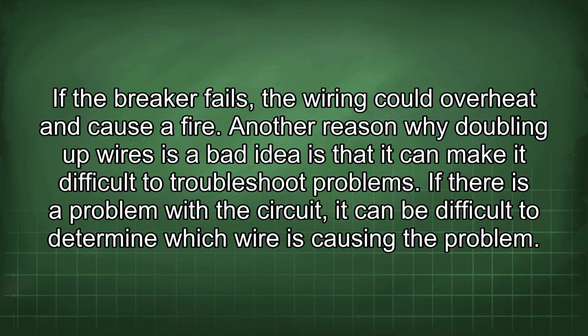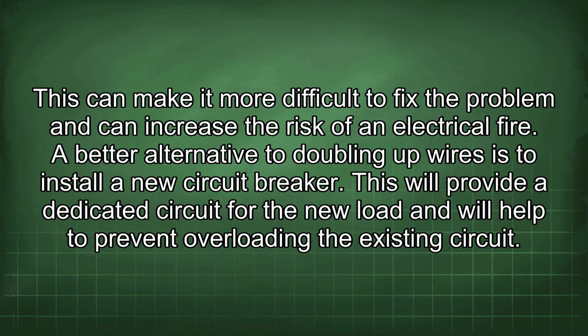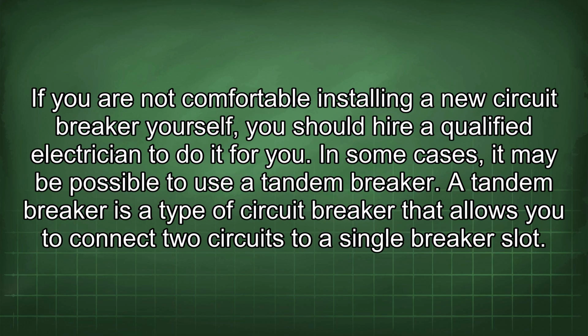Another reason why doubling up wires is a bad idea is that it can make it difficult to troubleshoot problems. If there is a problem with the circuit, it can be difficult to determine which wire is causing the problem. This can make it more difficult to fix the problem and can increase the risk of an electrical fire. A better alternative to doubling up wires is to install a new circuit breaker. This will provide a dedicated circuit for the new load and will help to prevent overloading the existing circuit. If you are not comfortable installing a new circuit breaker yourself, you should hire a qualified electrician to do it for you. In some cases, it may be possible to use a tandem breaker.